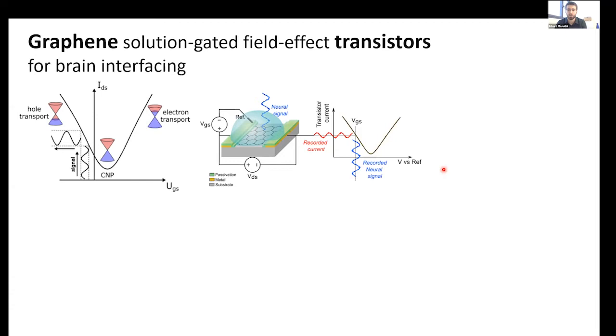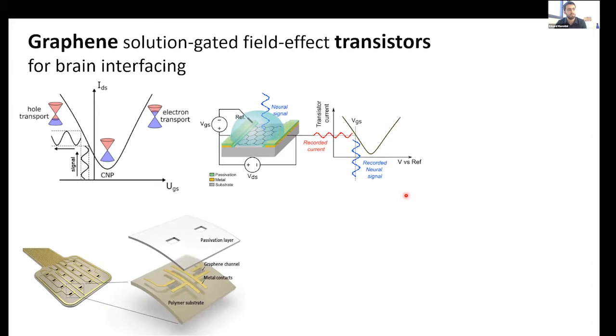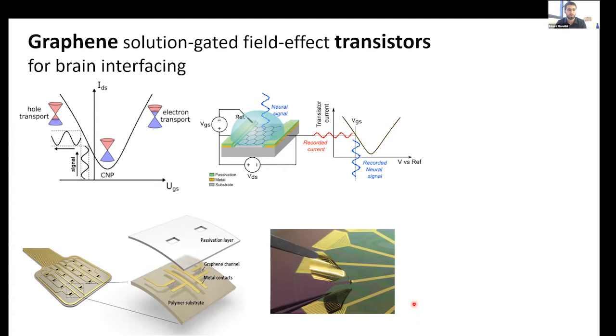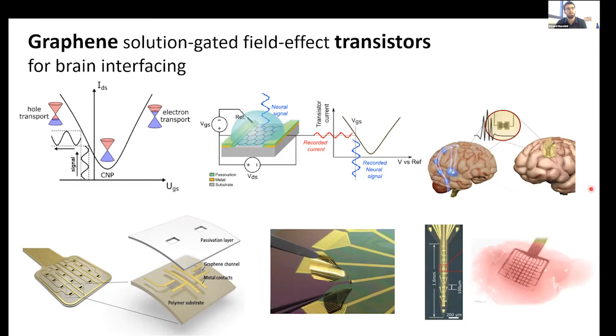Therefore, we can use graphene in what is called solution-gated field effect transistors, in which graphene forms the channel of a transistor and is in direct contact with the electrolyte. Neural signals in close vicinity to a transistor are converted into current modulations. We have spent several efforts developing flexible microelectrode arrays of graphene transistors in a microelectronics-compatible way. Our current process uses polyimide as a substrate, metals are defined by liftoff, graphene is transferred and patterned, and then we encapsulate the devices with a photo-definable layer, all done at wafer scale.